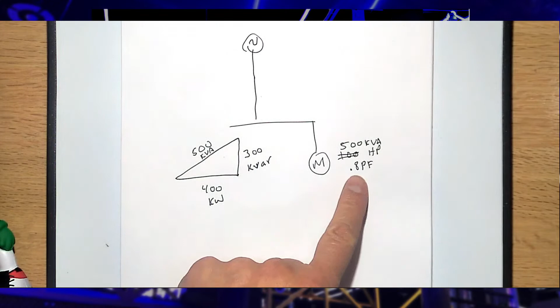That's the one thing most people who see this demo in their little suitcase don't get to understand, because when you draw the power triangle, you get a 3, 4, 5 triangle: 300, 400, 500 kVA, 400 kilowatts. One thing I learned about kVAR, Tom, in the IEEE standard, is it's small k, small v, a, r, not capital K. I always capitalize it wrong. So anyway, 3, 4, 5 triangle: 400 kilowatts, 300 kVAR, 500 kVA, because it's 0.8 power factor.